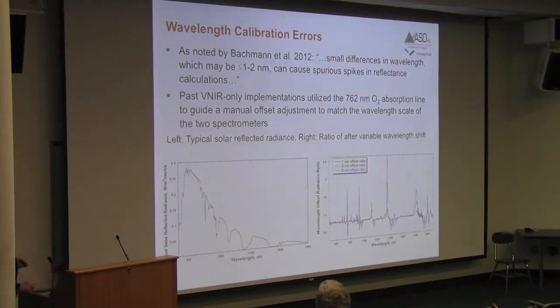Here's another example of why you want to align the spectral resolution scale very closely. Here's a solar spectrum with all its sharp features in it. If you just offset a little bit in ratio, you get all these spikes. So if you had two spectrometers you were using together, you really need quite precise wavelength scale intercalibration in order to get a reasonable result.